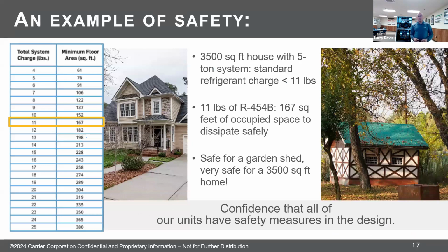Let's look at an example. You have a 3,500 square foot house. You put a 5-ton system in it. Let's say that 5-ton system has 11 pounds of refrigerant, just for example. At 11 pounds, if you look at the chart, you would need 167 square feet of space to dissipate that refrigerant safely, to get the refrigerant to air ratio down below the lower flammability limit. So 167 square feet, about the size of a garden shed. In a 3,500 square foot house, you have more than enough space to dissipate that refrigerant so that we eliminate or mitigate the flammability concern. As these products come out, homeowners are going to hear things on the internet about how dangerous it is. This is information you can share with them to give them a level of comfort.